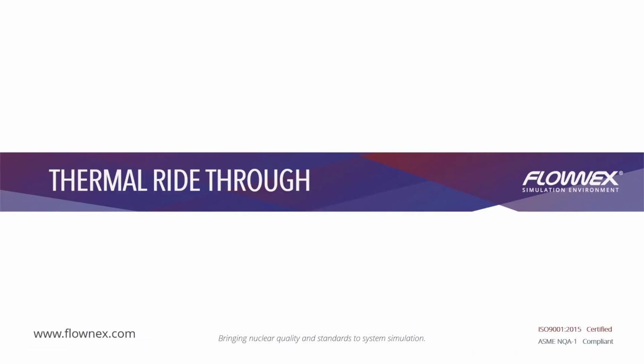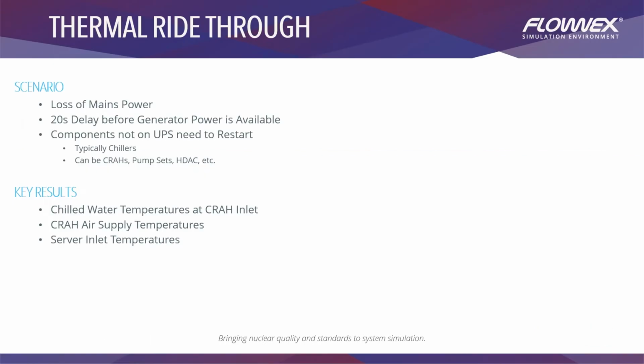So moving on to the main focus of our webinar today, we'll be looking at a thermal ride-through. By a thermal ride-through, I'm specifically talking about a loss of mains power and a transfer to generator power. This is sometimes also called a short break or a mains to generator transfer. Specifically, we're looking at the change in temperature in the chilled water in the system.